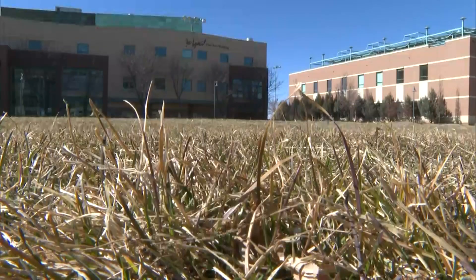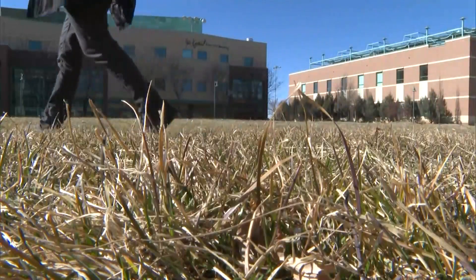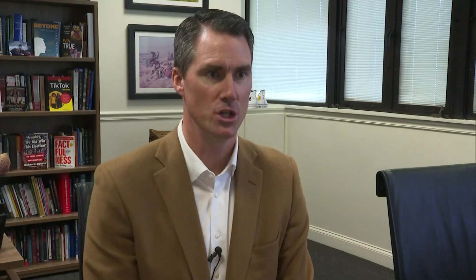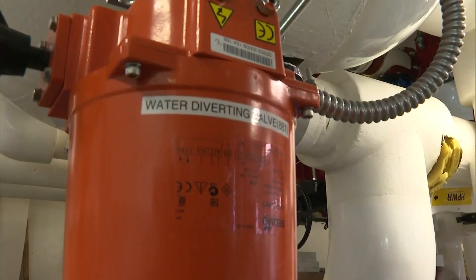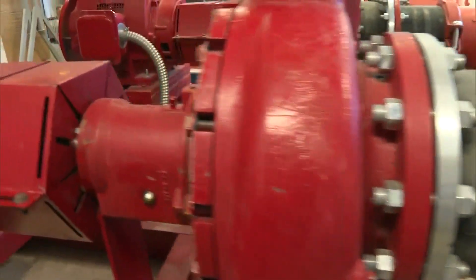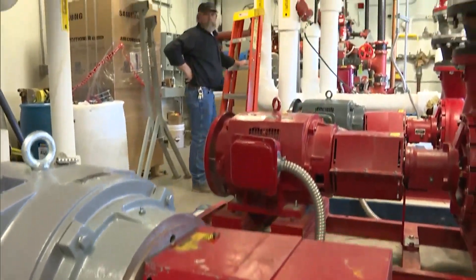On the western slope, they've got a high water table, which Colorado Mesa University has tapped into to heat and cool their campus. Geo-exchange technology — just a closed loop of water that runs through a series of pipes and helps heat and cool. The groundwater temperature never changes, so when it's too hot in the summer, they get cold from below, and then vice versa for winter.